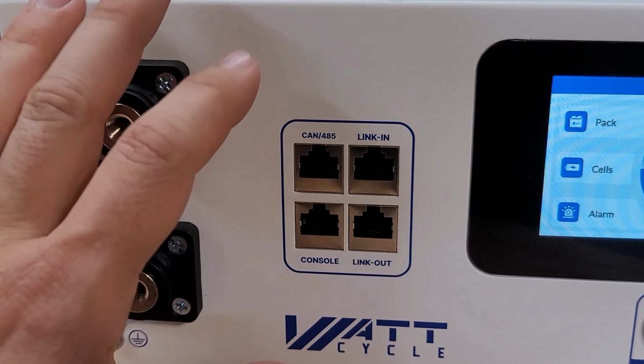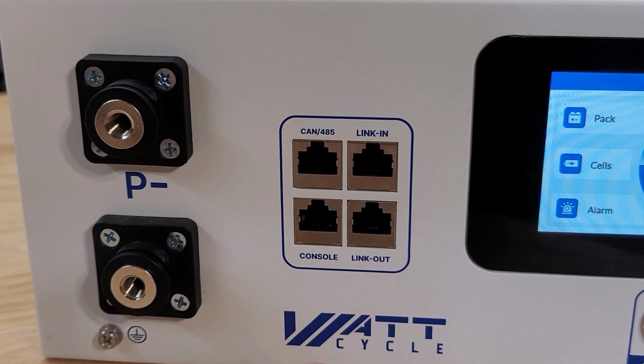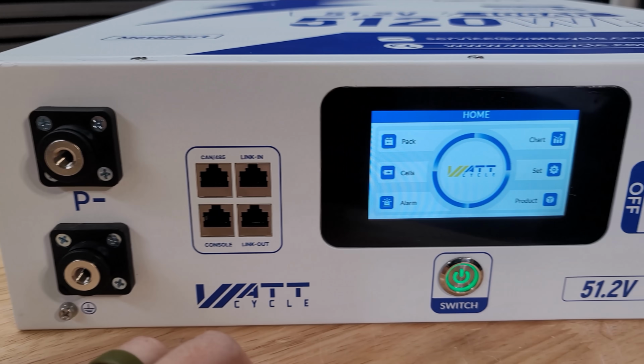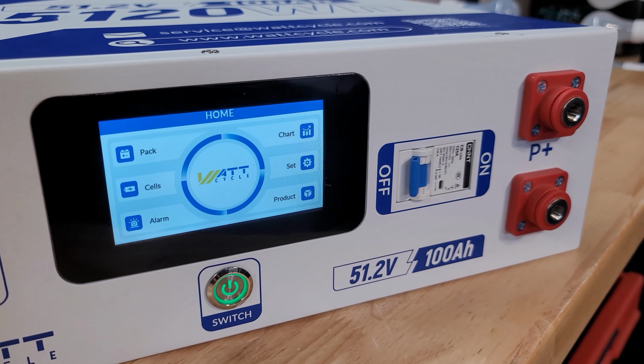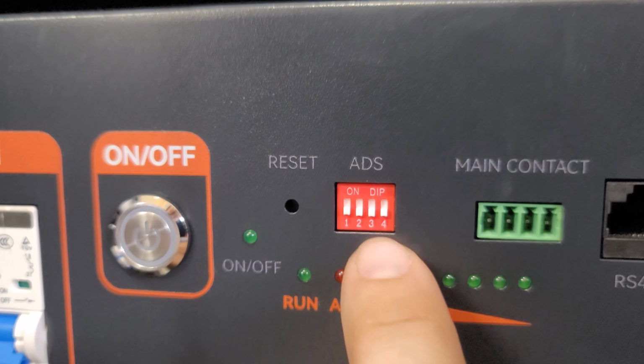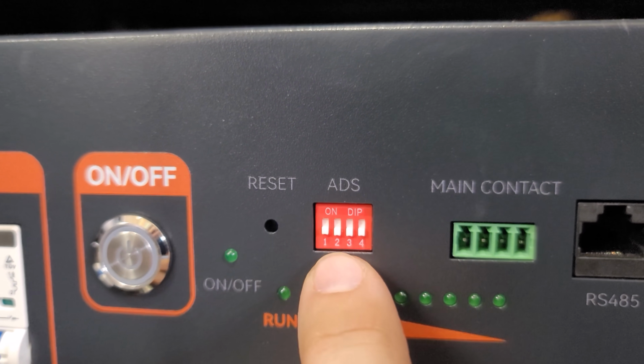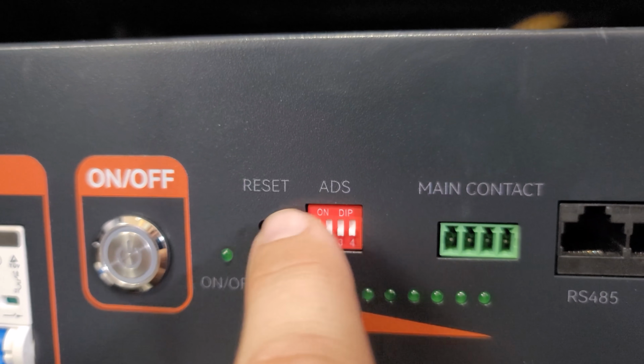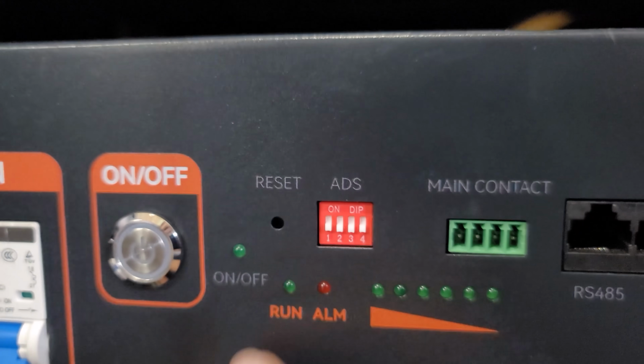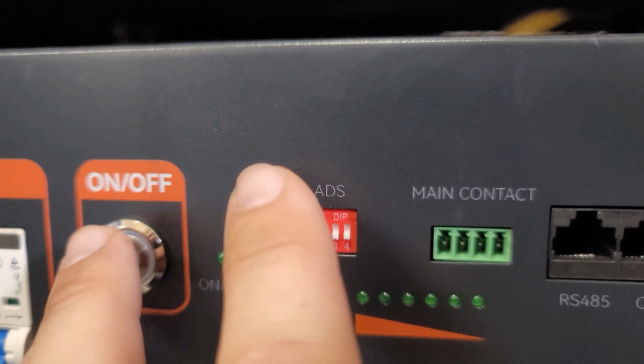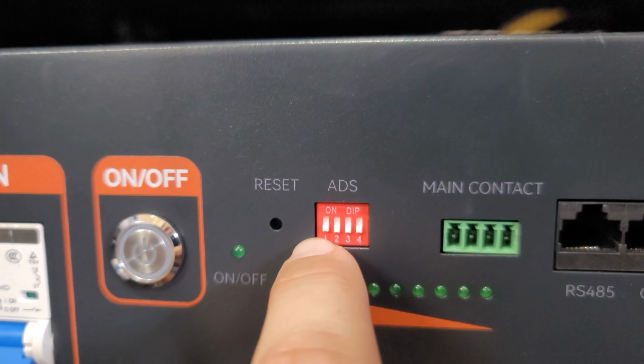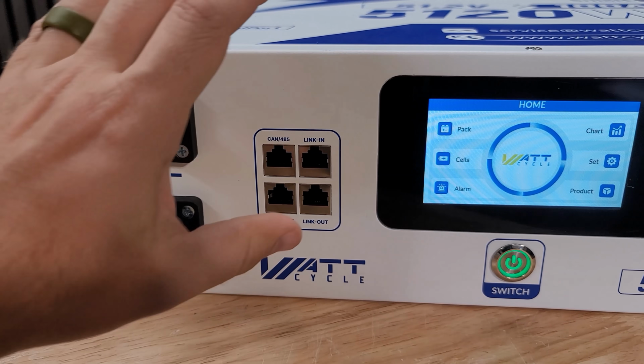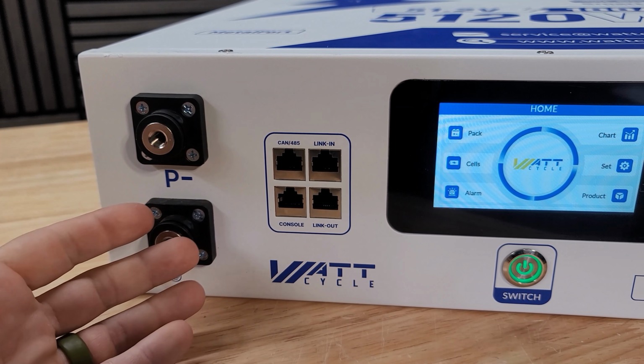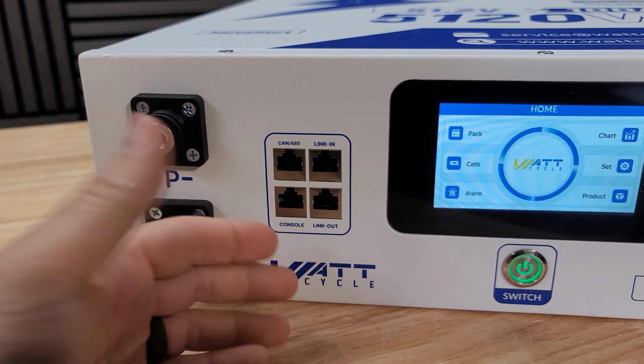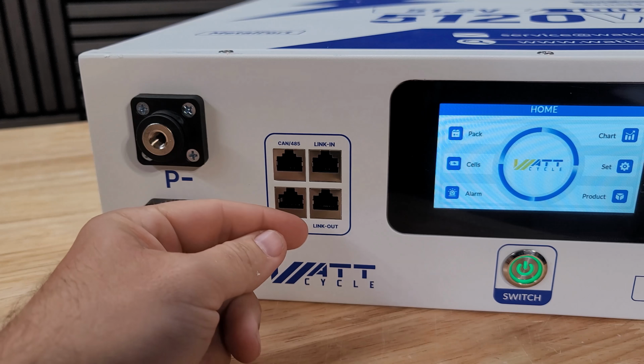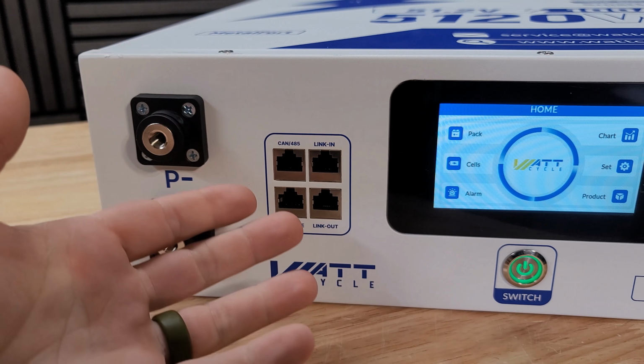One of the things that's really different about this battery is there are no dip switches along the front here. This is a dip switch, and what it allows you to do is tell each BMS and each battery which battery this is in the string of other batteries. So this could be battery 1, and you could change these dip switches to be battery 2, and so on. But for WattCycle, you don't have to use dip switches, which is a convenience because it's easy to accidentally offset one of those little switches and then it doesn't communicate properly.